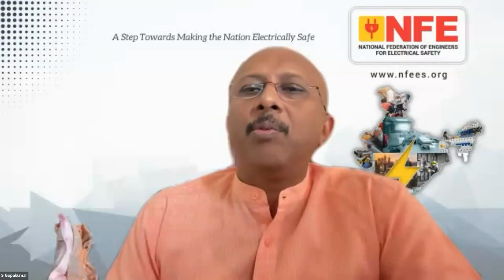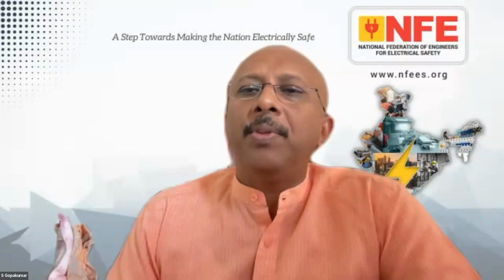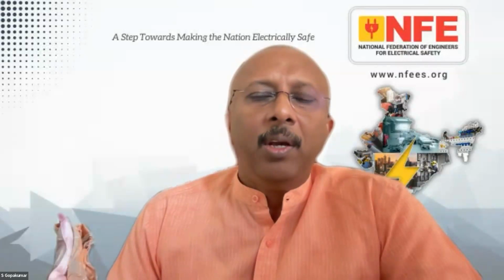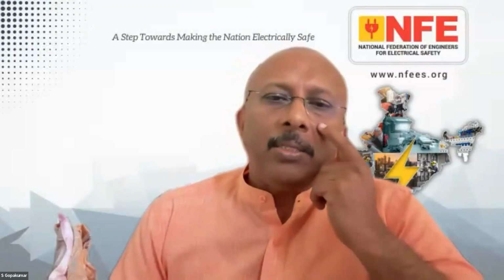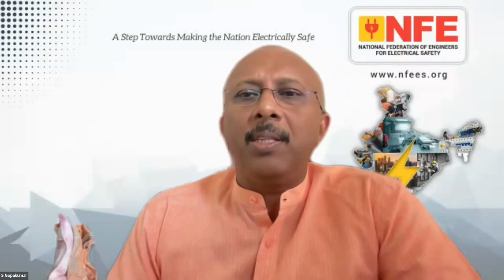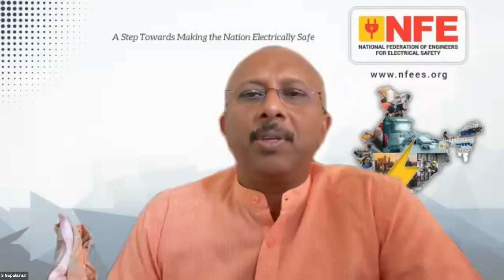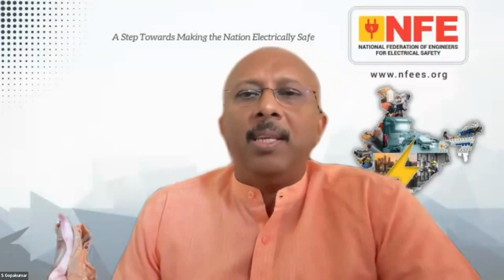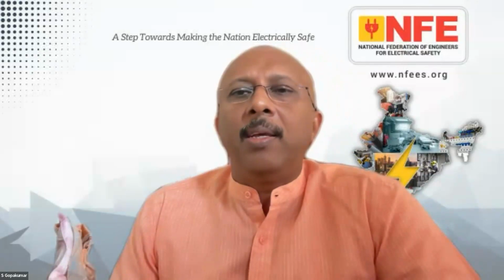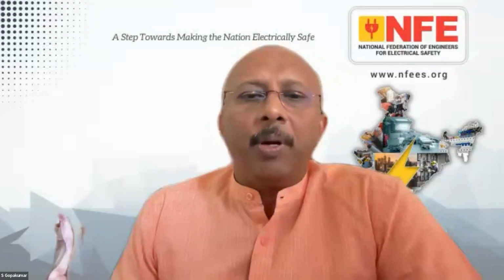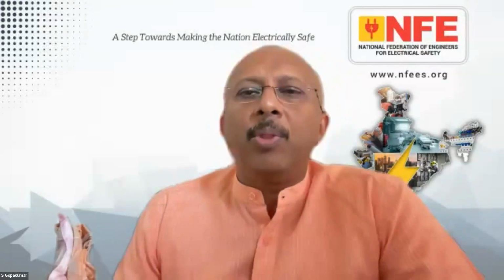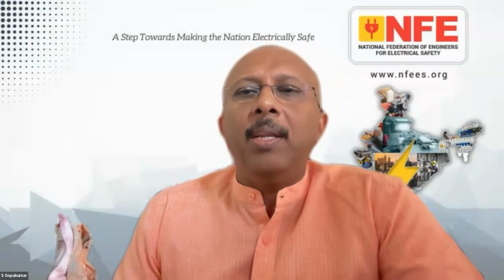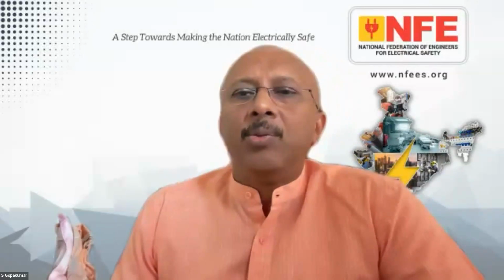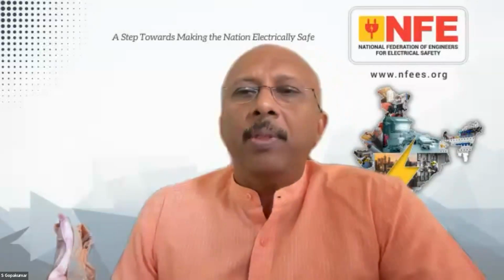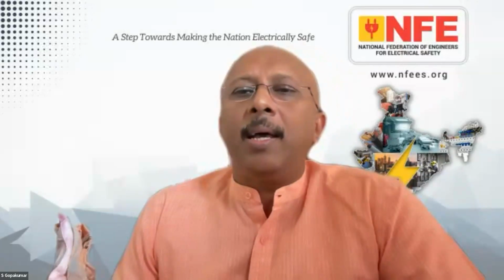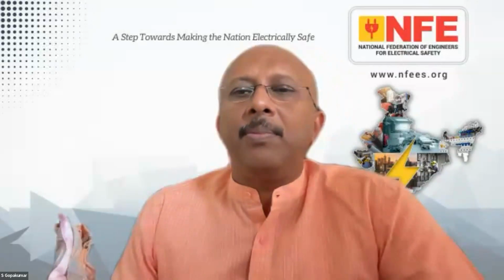So, Mr. Gurucharan Singh, how can we improve an old earthing system with minimum financial input? Actually, for making this improvement, it's not an expensive thing. It's probably 2-3 thousand rupees. You can change from TT to TN-C-S or TN-S. You have to interconnect the exposed and extraneous conductive parts. Never connect neutral to the other. Neutral shall be an insulated conductor. Very strict. If you can write to me with the single line diagram, probably I can answer or make some changes and give it to you.